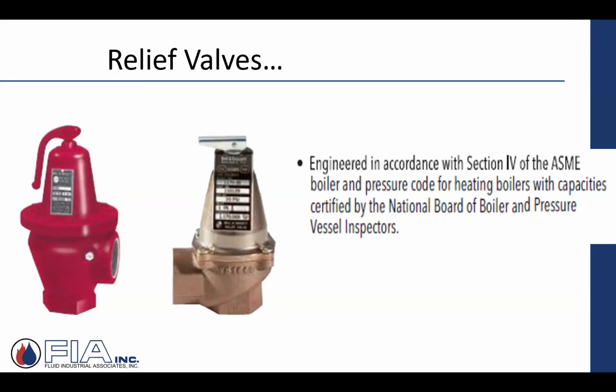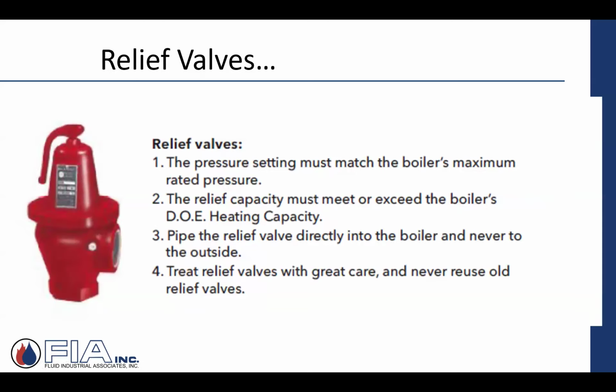Hopefully it's never active. Hopefully it's never needed, but it's there for a reason. It's engineered in accordance with Section 4 of the ASME Boiler and Pressure Code, certified by the National Board of Boiler and Pressure Vessel Inspectors. It's a pretty important device, very important device. It has two capacities that it needs to meet, two settings, if you will, when they're selected.